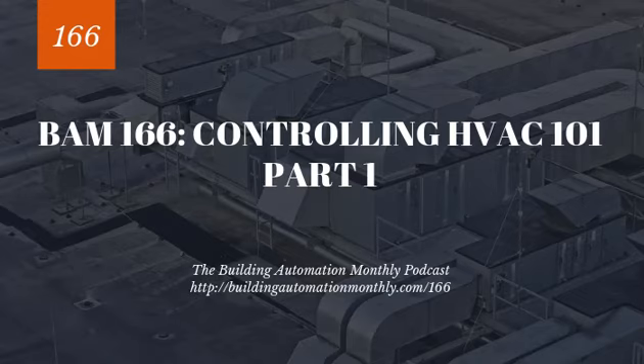And then you have exhaust. Now, you have a couple different kinds of exhaust. You can have just an exhaust fan that's static CFM, it runs, and you just have to account for the fact that this exhaust fan is always going to be exhausting this amount of CFM. Or you can potentially have exhaust VAVs that are variable, and these can be tracking using that volumetric matching, or they can be tracking something else like pressure, doing a modulating offset. Maybe it's a volumetric offset where you're taking a direct minus from your supply, saying supply minus 200 CFM, and that's going to be my exhaust CFM set point.